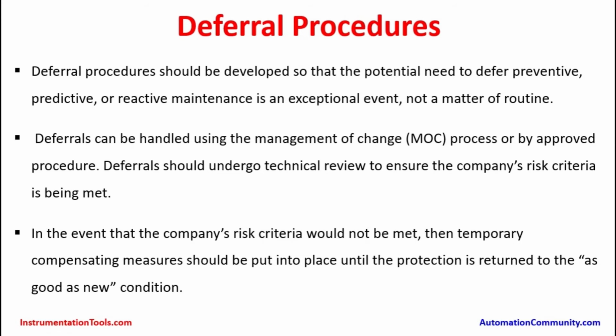Deferrals can be handled using the management of change process or by an approved procedure. Deferrals should undergo technical review to ensure the company's risk criteria are being met. In the event the company's risk criteria would not be met, then temporary compensating measures should be put into place until the protection is returned to as good as new condition. Whenever the safety risk criteria which is already designed cannot be met, there could be a requirement to make alternative or compensating measures.